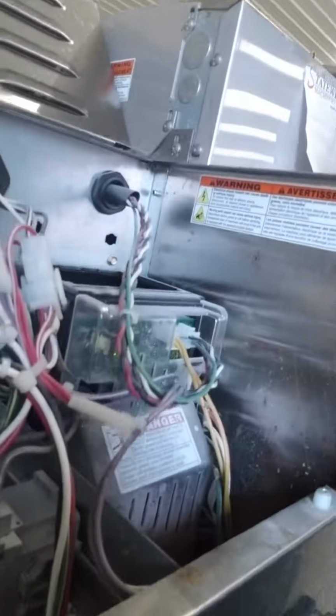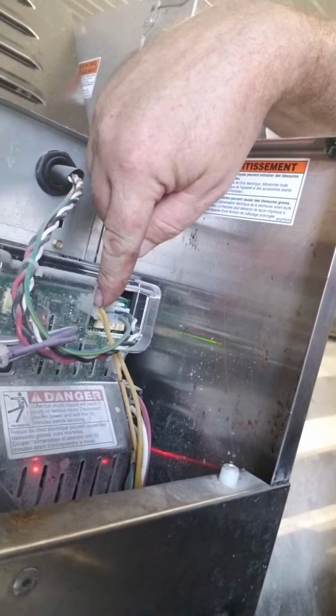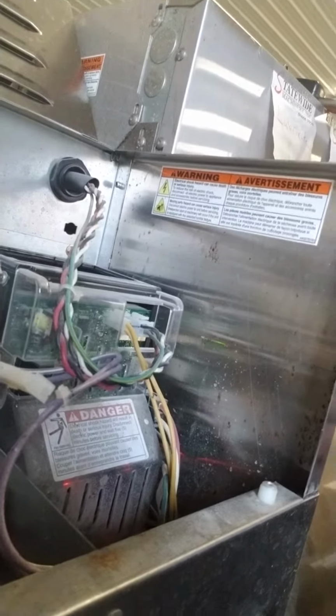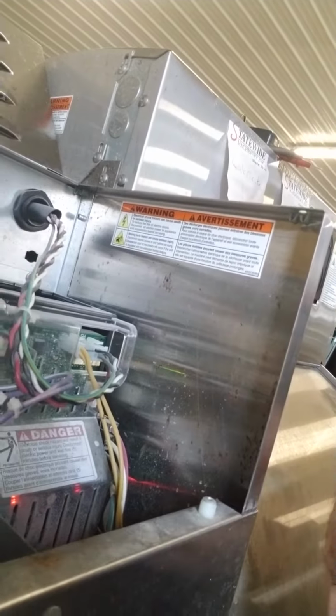There are two little yellow wires right here. I'm going to take those off and check them to see if I have around 300 ohms resistance coming back through those while my motor's turning. If I have that resistance, then the motor's fine and the drive is bad. If I do not have it, then the motor's bad, and hopefully the drive is good.